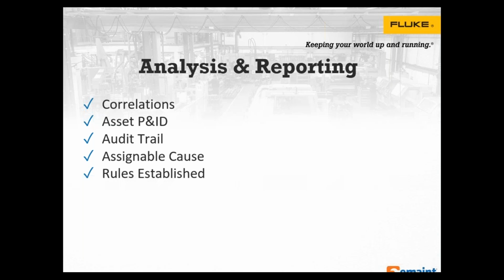It's good to know that there's something going on, but you want to establish these rules, and this is really an evolution. This is what I've seen. My experience is it's like an evolution for some assets to get to the right type of reaction for that particular asset. In some cases you may want to just go do a quick check on it and maybe do a resample and see if it comes in again. And it could be variability in the operator, how they're taking that particular measurement. It could be human error when the data point's entered. It has to do with the integrity of data coming in.